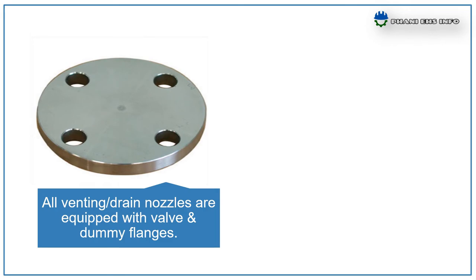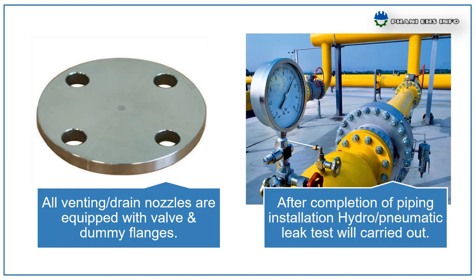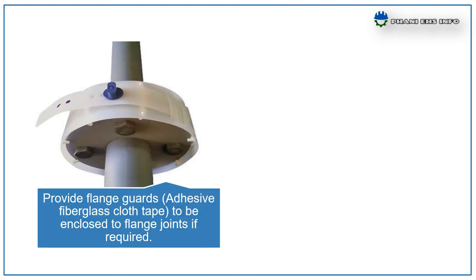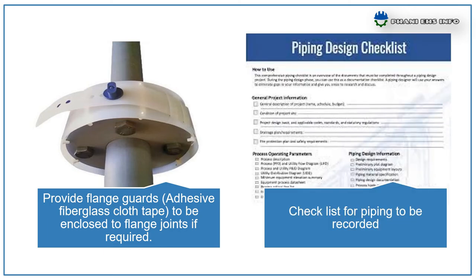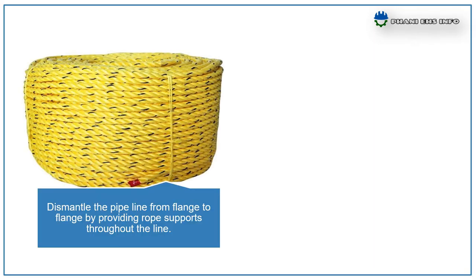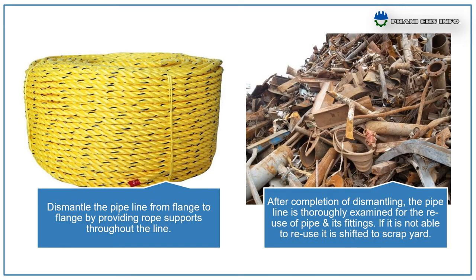All venting or drain nozzles shall be equipped with a valve and dummy flanges. After completion of piping installation, hydro or pneumatic leak testing will be carried out. Provide flange guards to enclose flange joints if required. A checklist for piping shall be recorded. Dismantle the pipeline from flange to flange by providing rope support throughout the pipeline. After completion of dismantling, the pipeline is thoroughly examined for reuse of pipe and its fittings. If not suitable for reuse, it is shifted to the scrapyard.